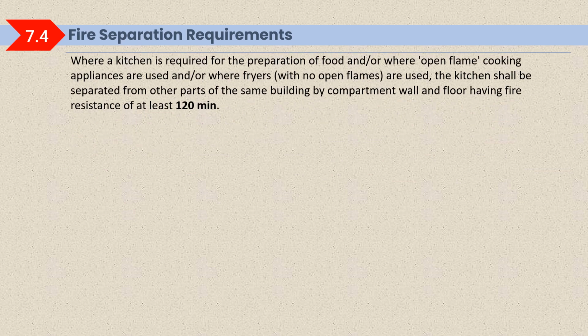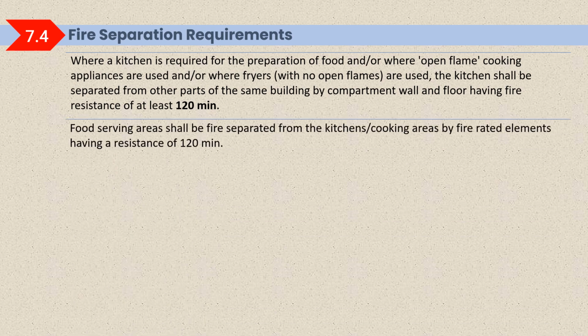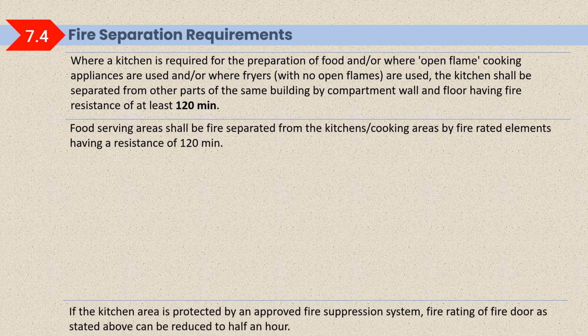Where a kitchen is required for the proper preparation of food, and or where open flame cooking appliances are used, and or where fryers with no open flames are used, the kitchen shall be separated from other parts of the same building by compartment. So we are talking about the separation requirement. The compartment wall and the floor shall have fire resistance of at least 120 minutes. Food serving area shall be fire separated from the kitchen cooking area by fire rated elements having a resistance of 120 minutes.